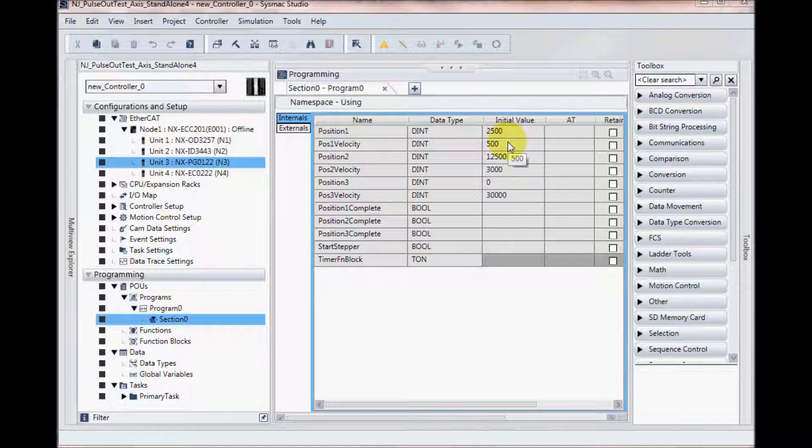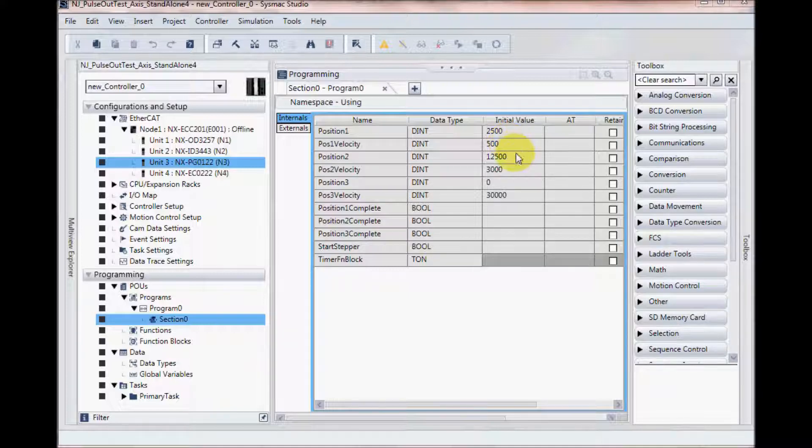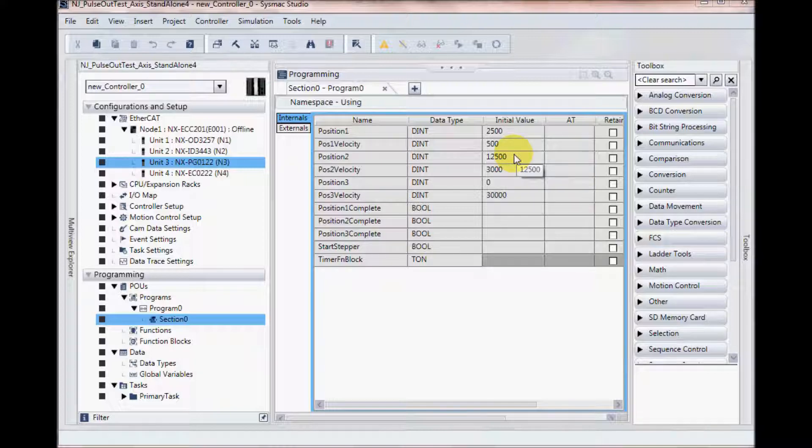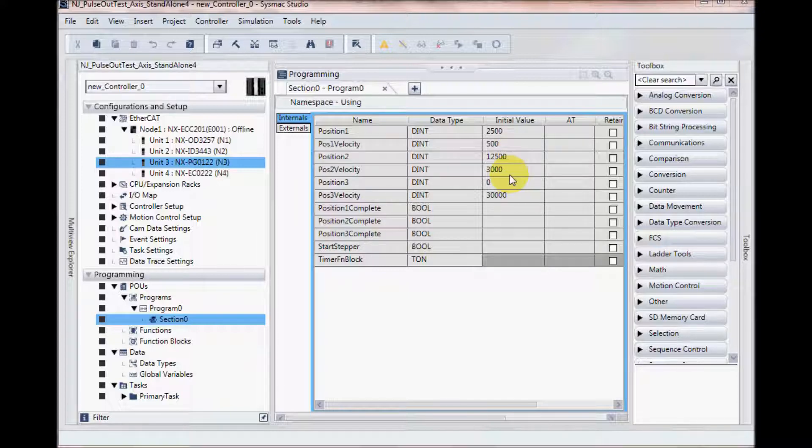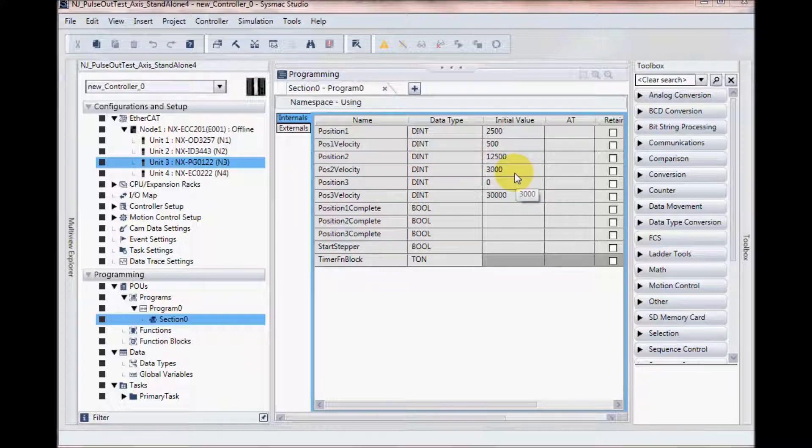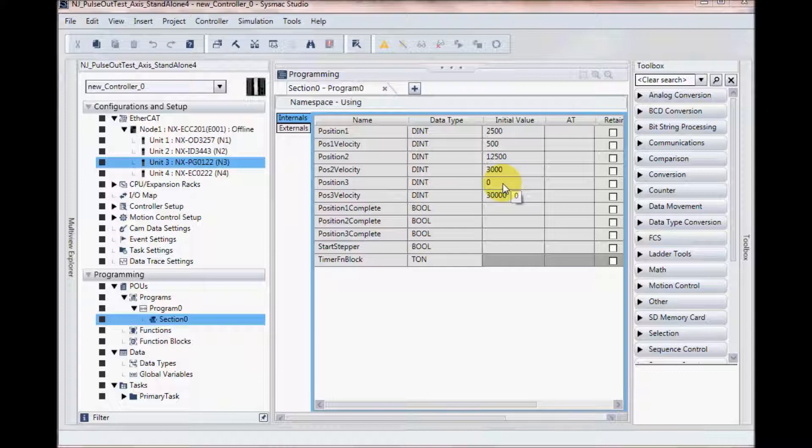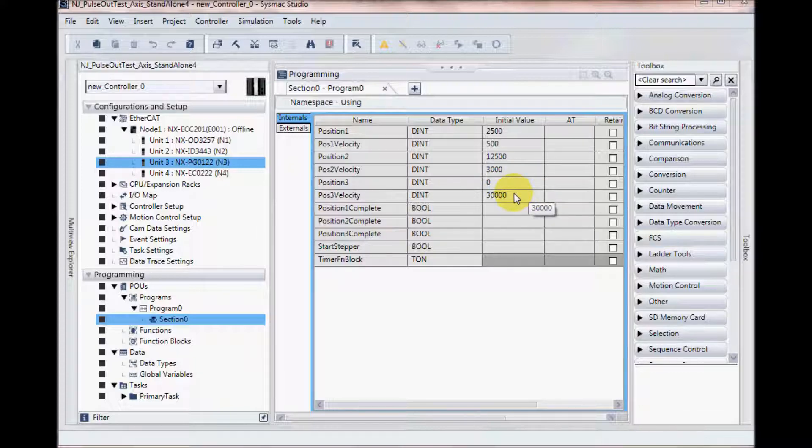My next position is going to be 12,500, and so I will be going 4 more revolutions from my existing position. My speed is going to be 3,000 pulses per second, and my last position will be 0 or my home position, and I'll go at 30,000 pulses per second.